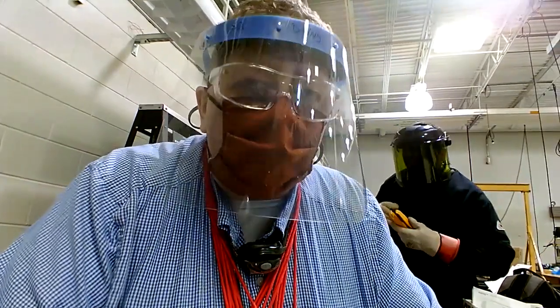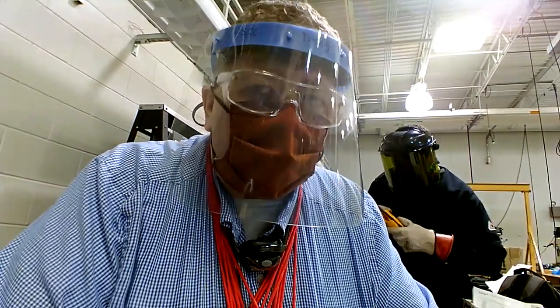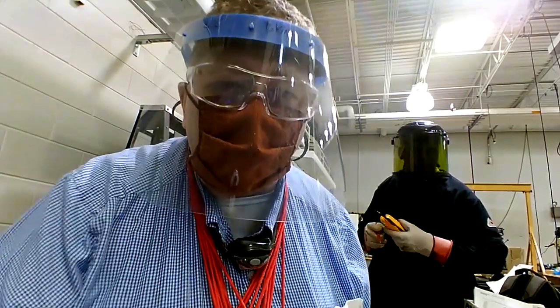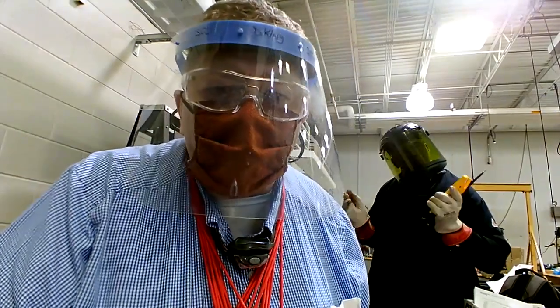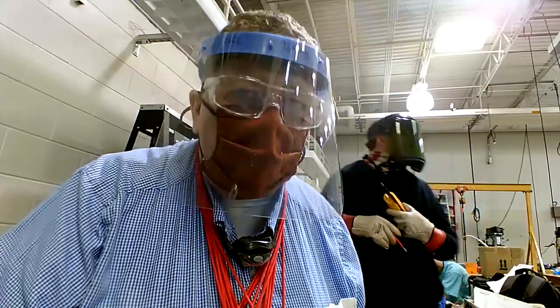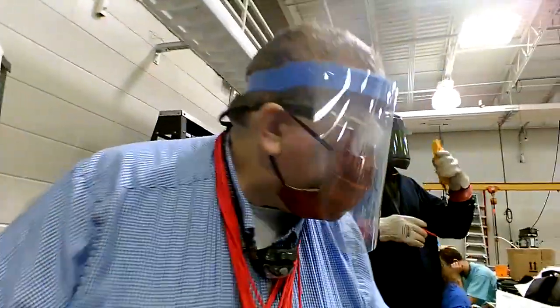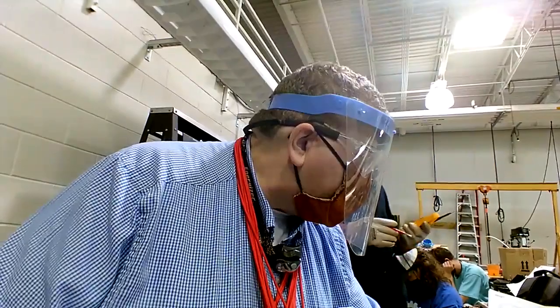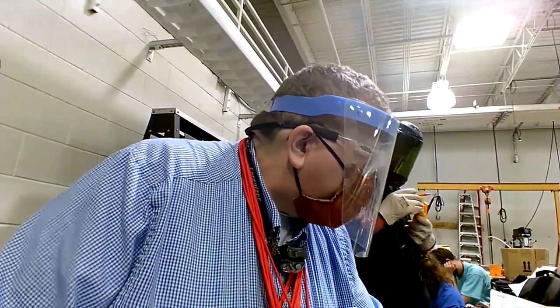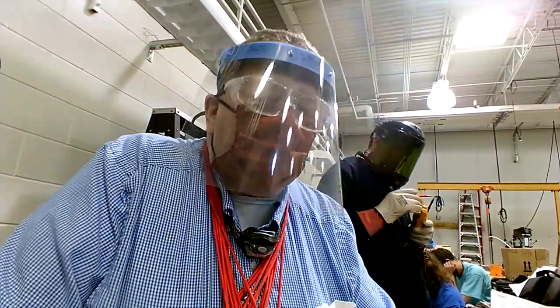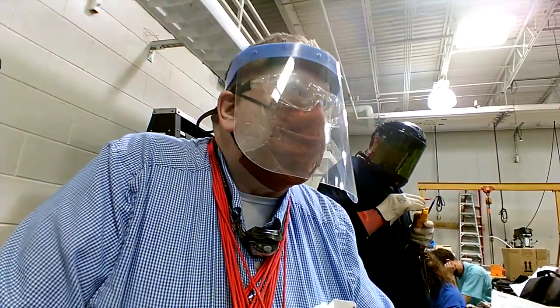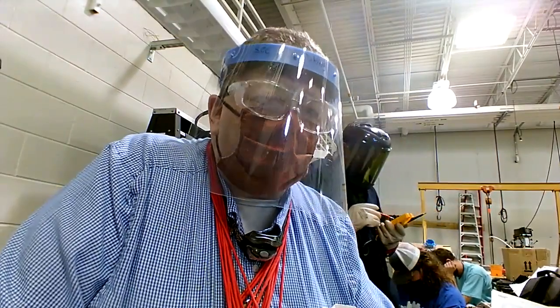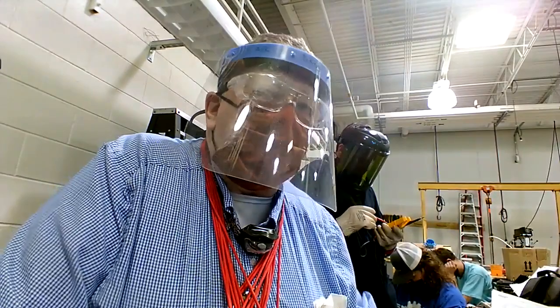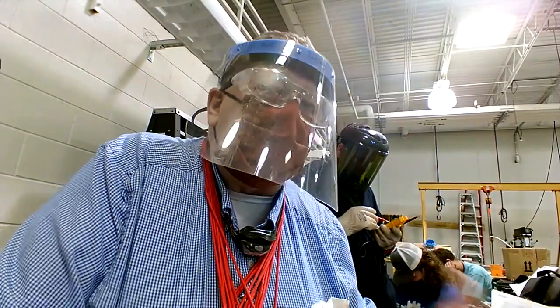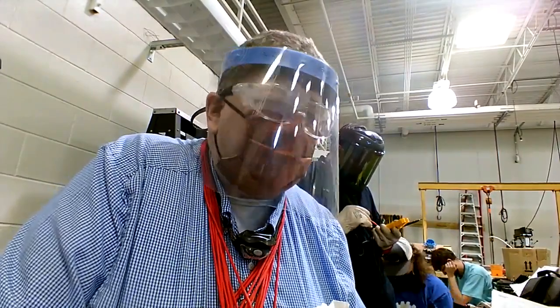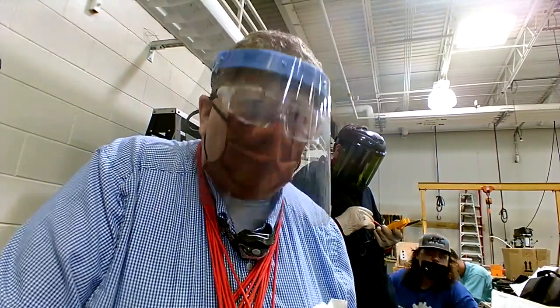So this is Durward King of Samson Community College. This is ELC 117 motor control on March the 10th, 2021. And we're in chapter 6, and we're going to look at something that deals with transformers, on the secondary of your transformer, where our 120 volt is for our controls. Some transformers are grounded on the secondary on the neutral, and some are not. If it's grounded, it's called a grounded secondary. If it's not grounded, it's called floating.